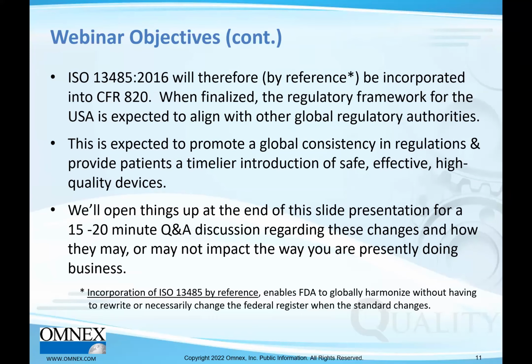ISO 13485 will, by reference, be incorporated into CFR 820. When finalized, the regulatory framework for the USA is expected to align with other global regulatory authorities. Now, incorporation by reference, we'll have a slide later in the presentation to address the pros and cons of this concept. But what it does is enable the FDA to harmonize without having to rewrite or necessarily change all the Federal Registers when the standard changes. And we'll spend a little more time on that later in the presentation.